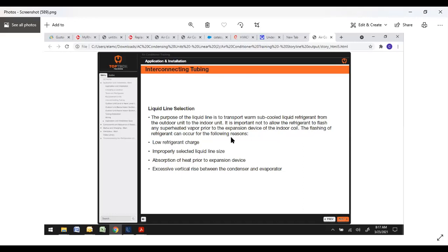It is important not to allow the refrigerant to flash any superheated vapor prior to the expansion device of the indoor coil. The flashing of refrigerant can occur for the following reasons: low refrigerant charge, improperly selected line size, absorption of heat prior to the expansion device, excessive vertical rise between the condenser and the evaporator. So it is important that you follow the line chart, what's permitted and what is not recommended based on your unit size and then also your length requirements.